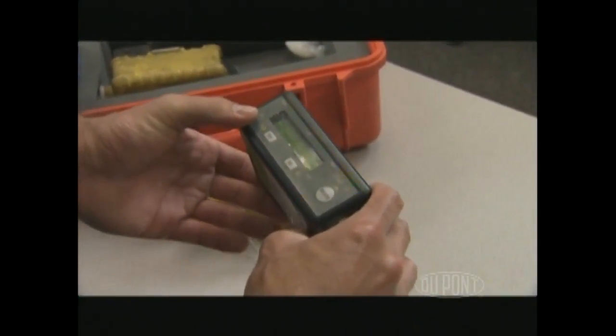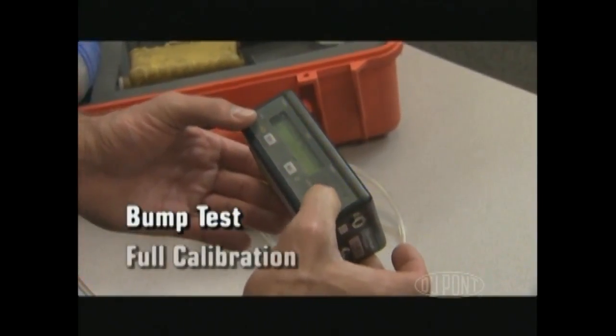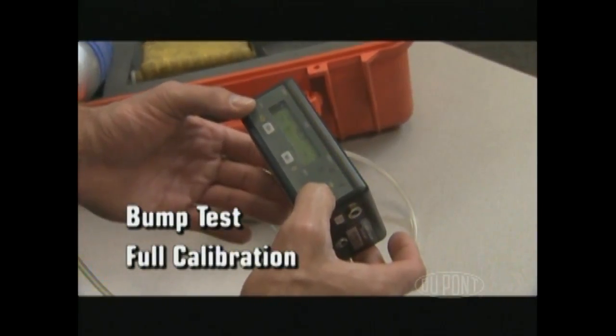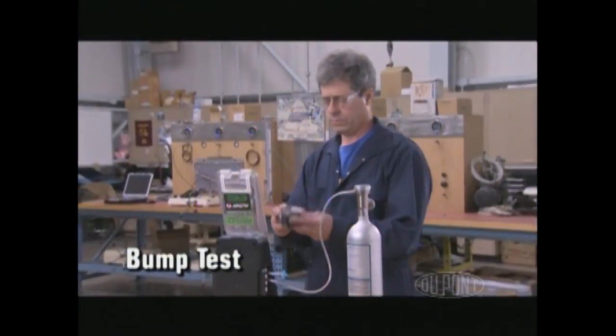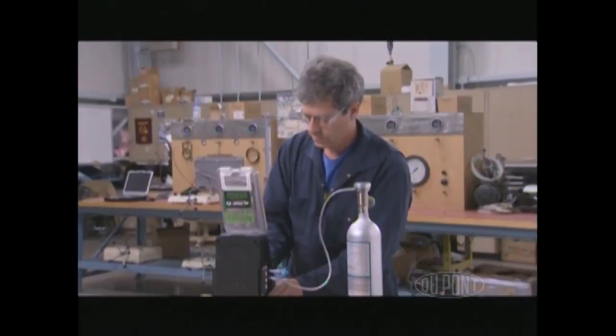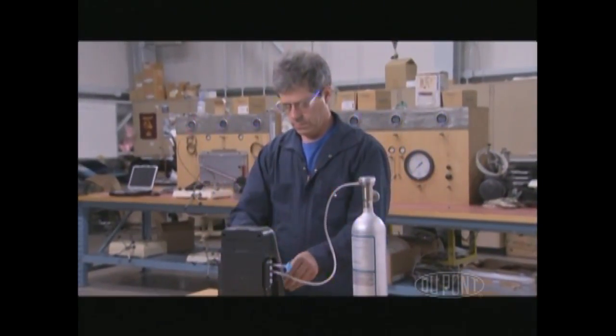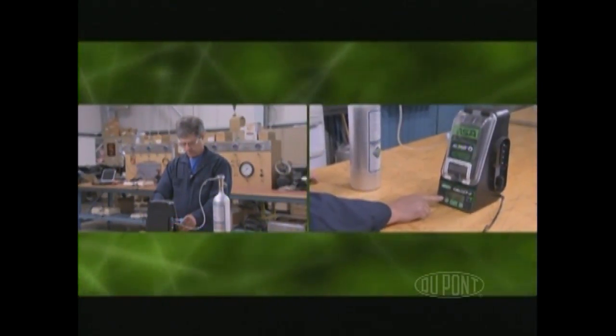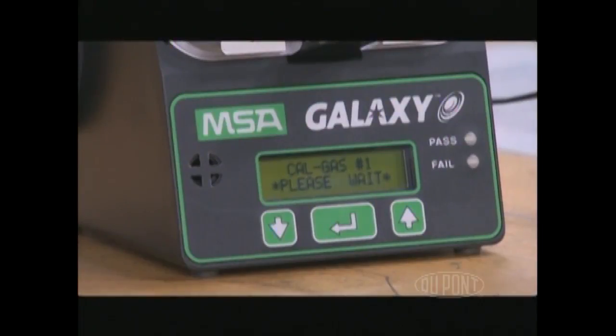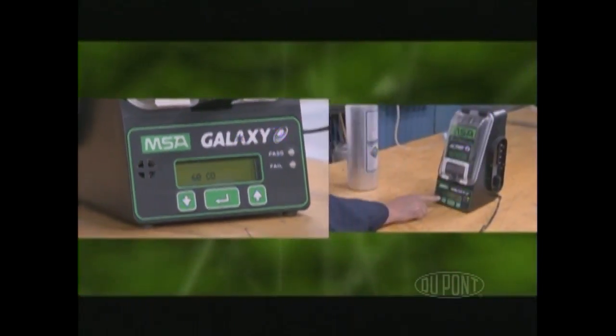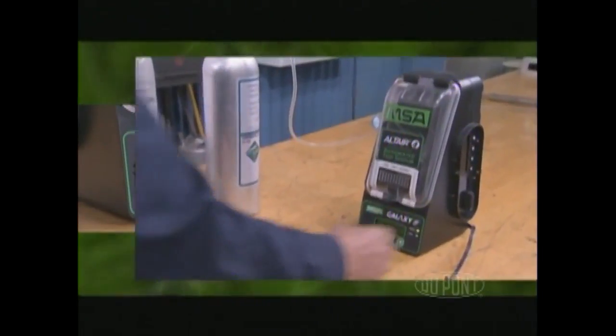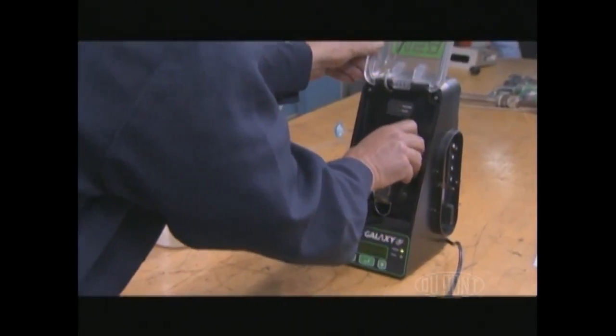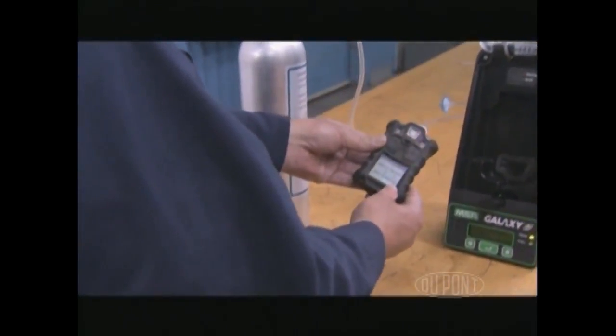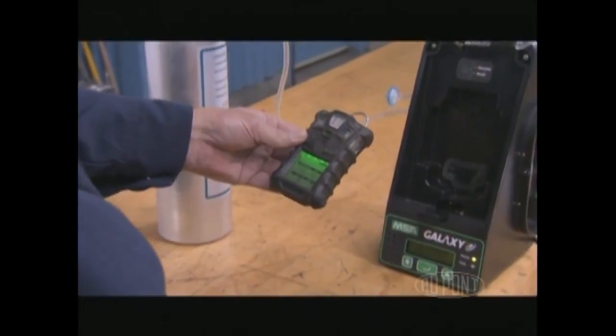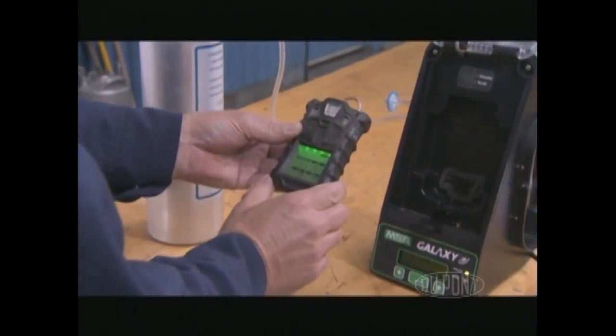The two methods of verifying instrument accuracy are the bump test and full calibration, both of which use a known concentration of gas. The bump test calls for the testing of the instrument in a clean, fresh air environment using a known concentration of gas. The instrument should be zeroed for greater accuracy and set to the appropriate tolerance range for the gas being used. If the instrument is working correctly, the alarm will sound upon exposure to the gas. If the instrument does not respond correctly or as expected, full calibration is necessary. Bump tests should be performed before each day's use and initial entry by a trained professional.